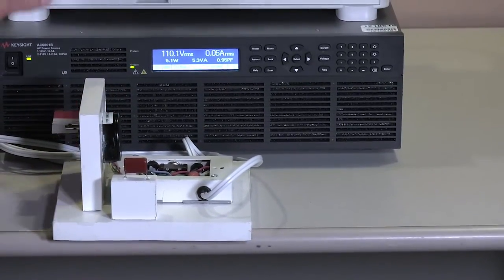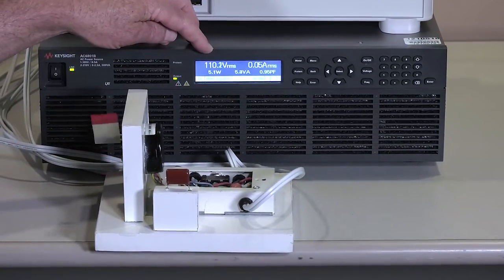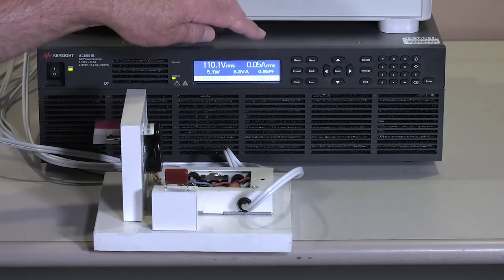Now our motor is being powered with our AC source. Our AC source is outputting 110 volts at 60 hertz, and as you can see the AC source is making several measurements of our motor, the power and also power factor.